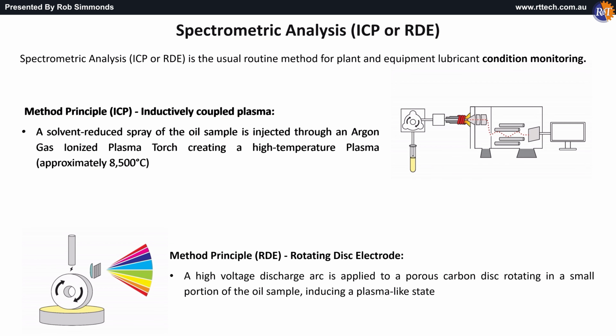Method principle: inductively coupled plasma, a solvent-reduced spray of the oil samples injected into an argon gas ionized plasma torch, creating a high temperature plasma of about 8,500 Celsius. Rotating disc electrode: a high voltage discharge arc is applied to a porous carbon disc rotating in a small portion of the oil sample, inducing a plasma-like state.